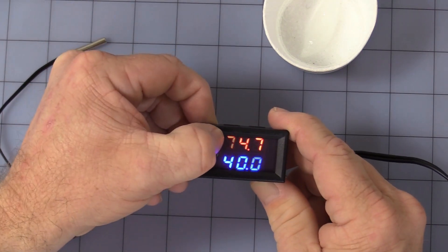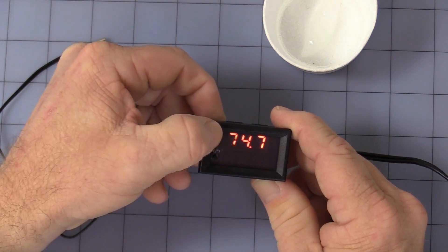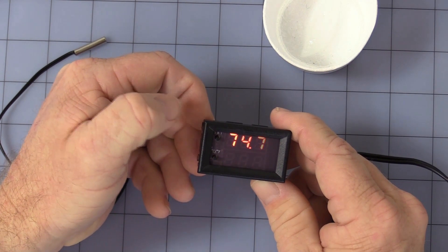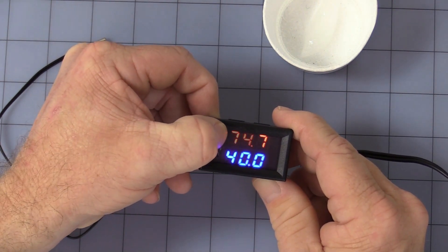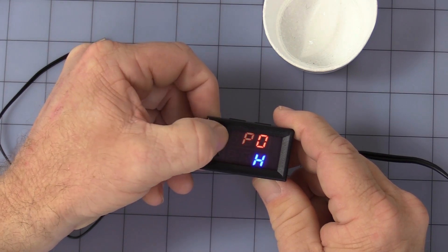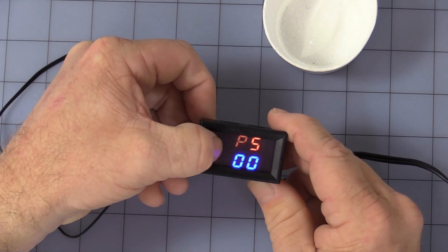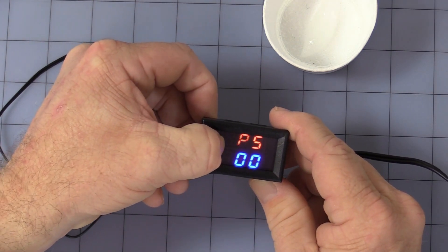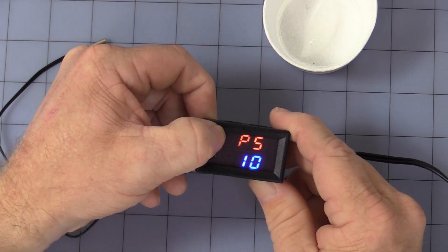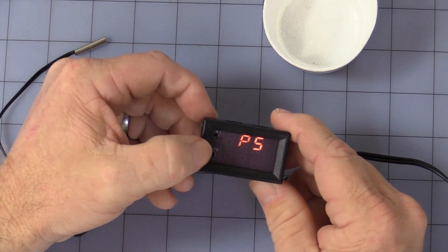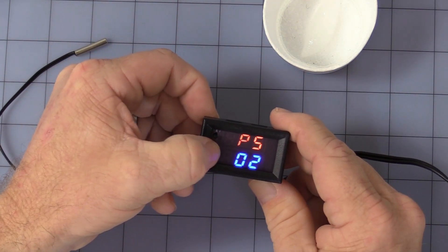Then we have P5, which is a delay turn-on. I've got to hold it long enough. P5 will give you up to a 10-second delay. Simply hold both buttons, then you see flashing, and you can adjust it up to 10 seconds. But it comes factory set at zero.